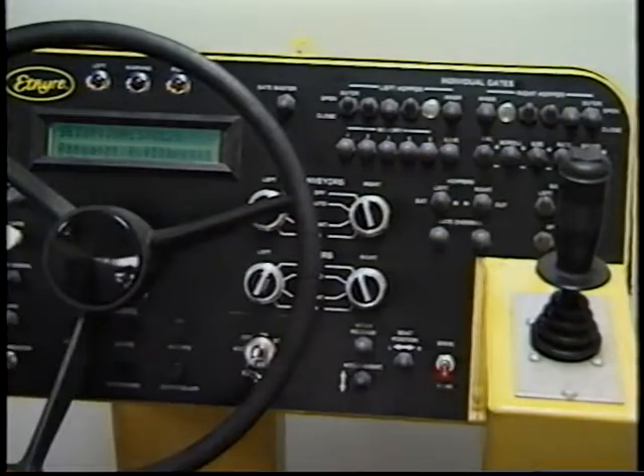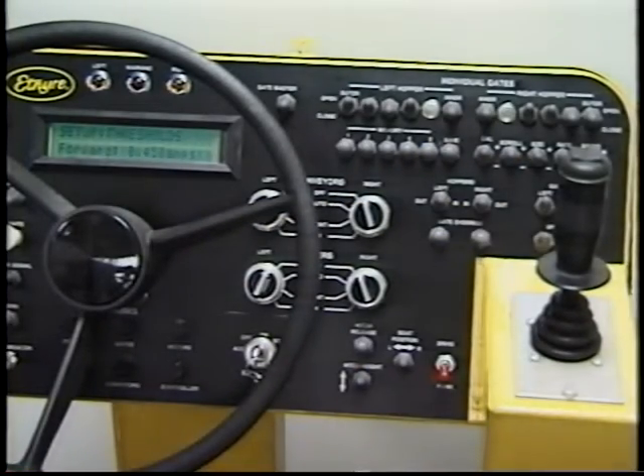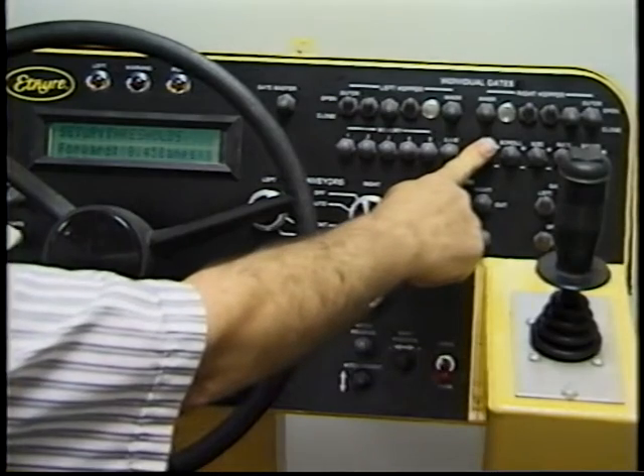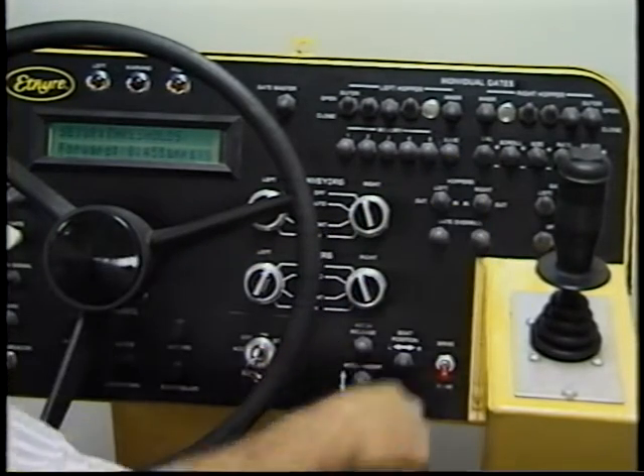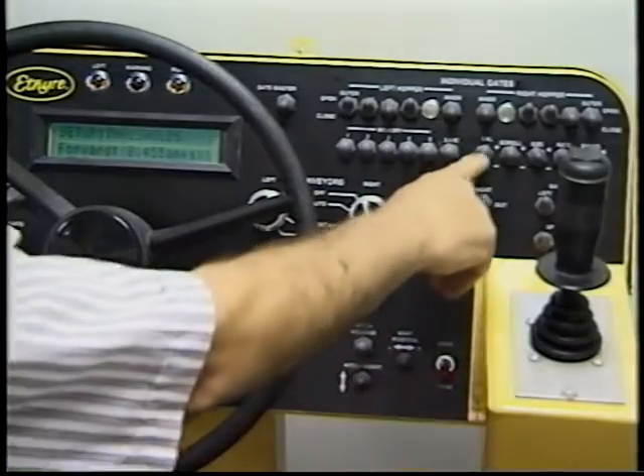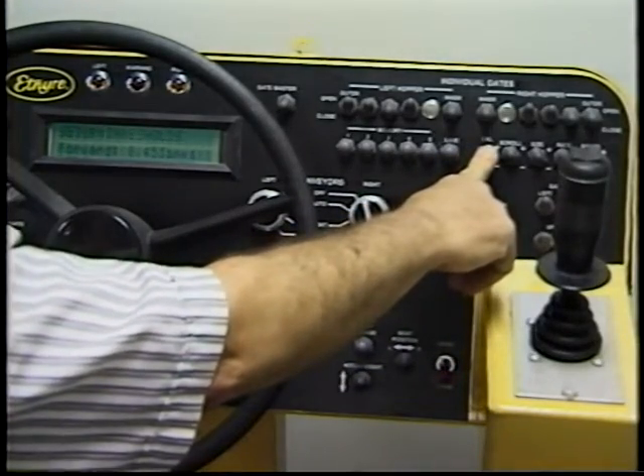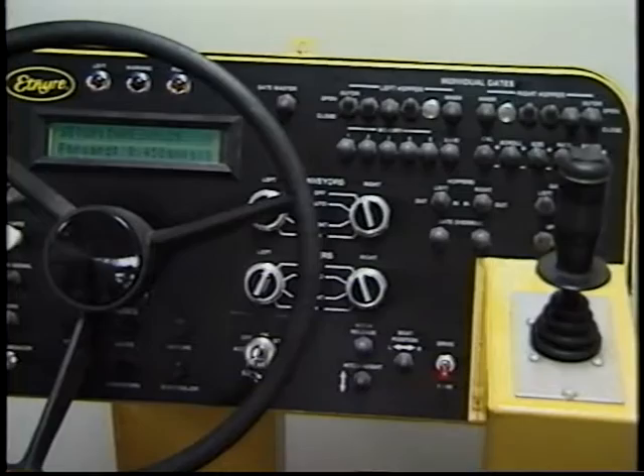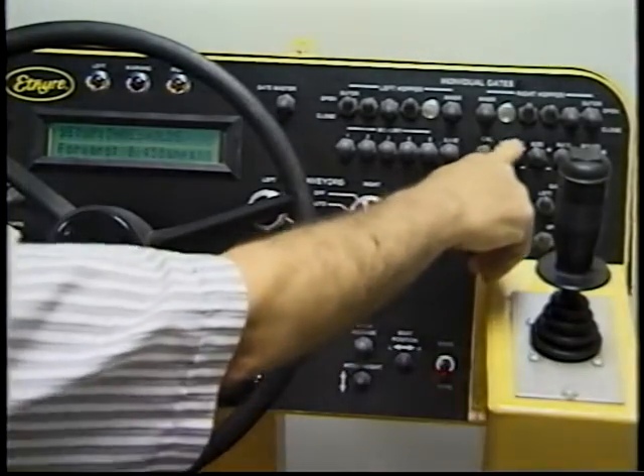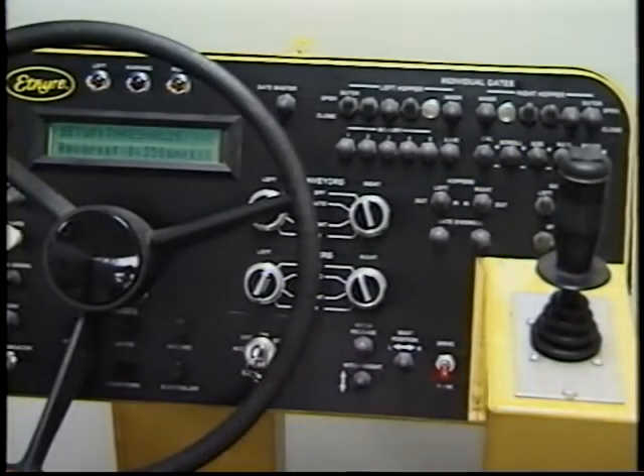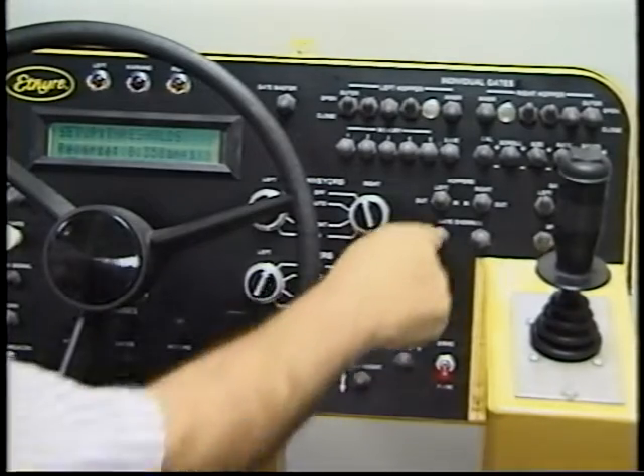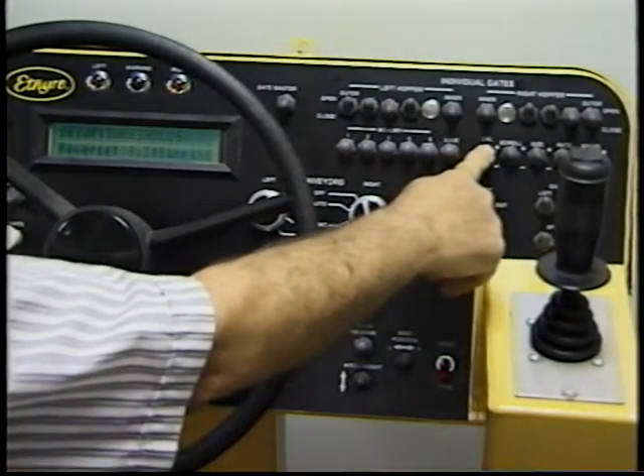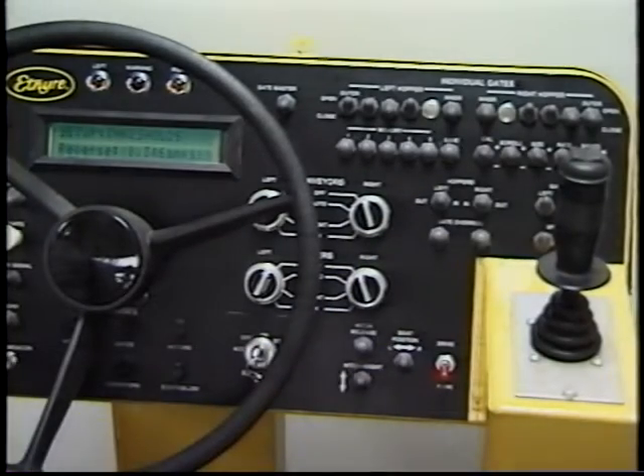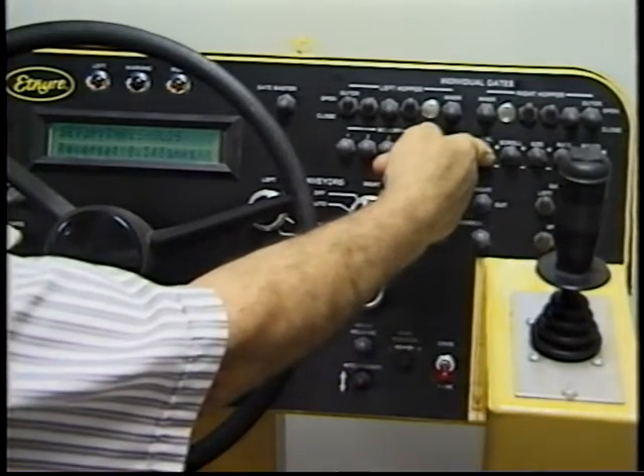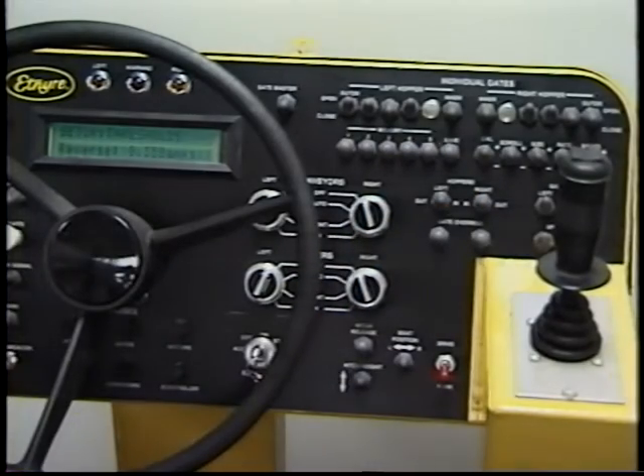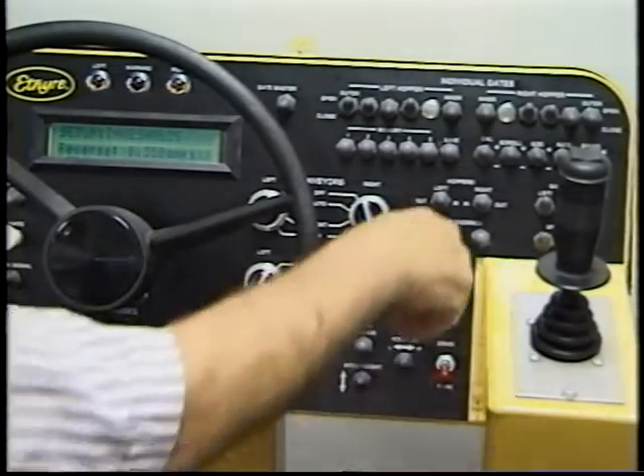This screen is used to set the threshold current to the forward solenoid on the hydrostatic pump. This value should be set to 0.450 amps using the CAL switch. When it is set to this value, push the scroll switch to move to the next screen. This screen is used to set the threshold current to the reverse solenoid on the hydrostatic pump. This value should be set to 0.350 amps using the CAL switch. When it is set to this value, push the scroll switch to move to the next screen.